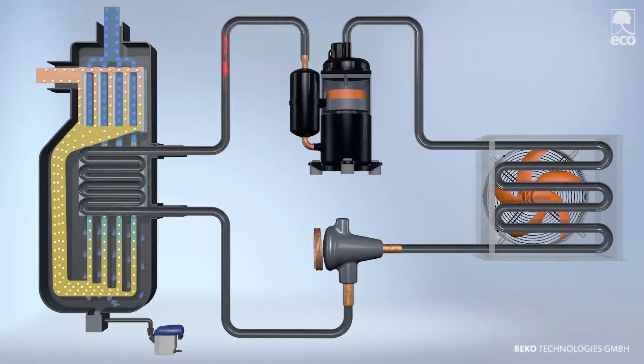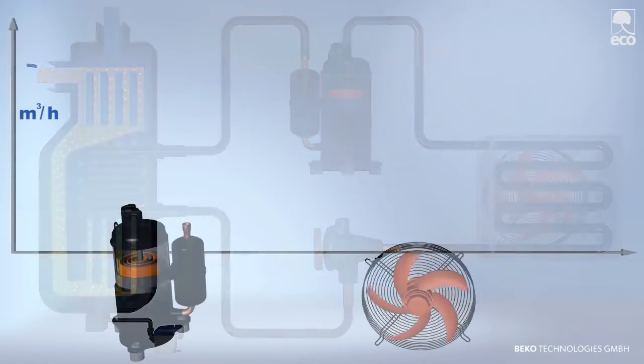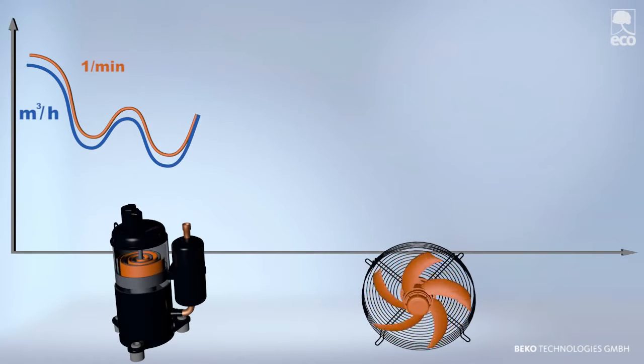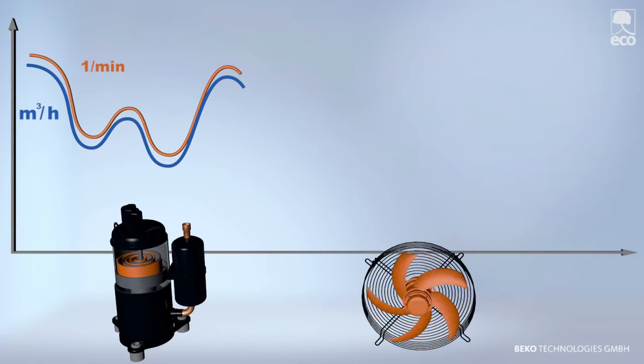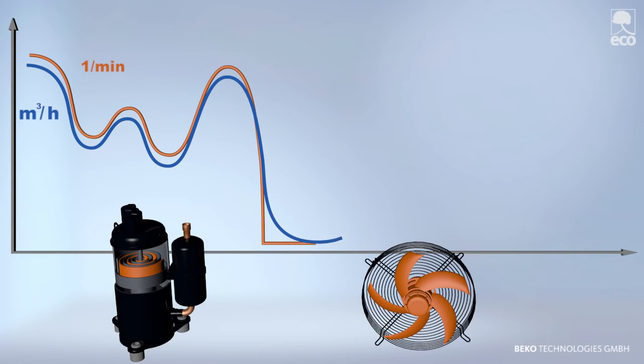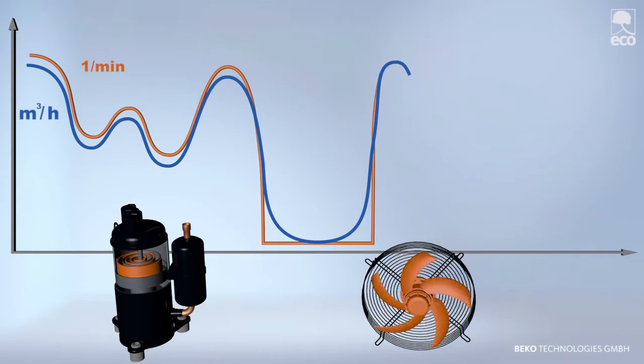In order to save energy when fluctuations in compressed air occur, such as flow volume, temperature, or pressure, the smaller versions of the DRYPOINT RA Eco switch the refrigerant compressor on and off to accommodate variations in the drying requirements. After reaching a certain system size, the drying performance is controlled by changing the frequency of the compressor, and thus even more finely adjusted to the volume flow.